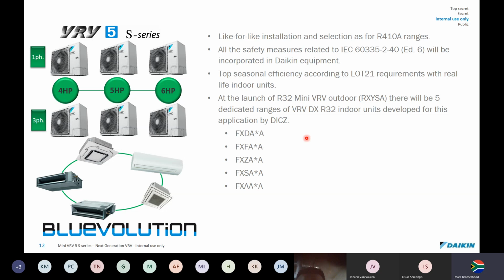And at the launch of R32 mini VRV outdoor units, there will be 5 dedicated ranges of indoors. I'll get on to this a bit later, but when ordering these R32 outdoors, Daikin have made a new indoor range. You cannot put 410 or existing indoor units onto the R32 range. It has to do with the safety alarms that are built into this new range. So if there's a leak, these new models will trigger an alarm telling you that it's detected a leak. So it's not backward compatible. The new range will also have new indoor units.